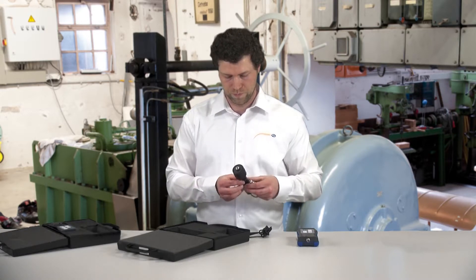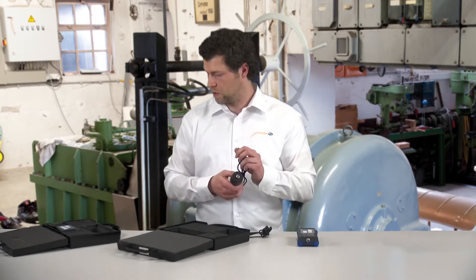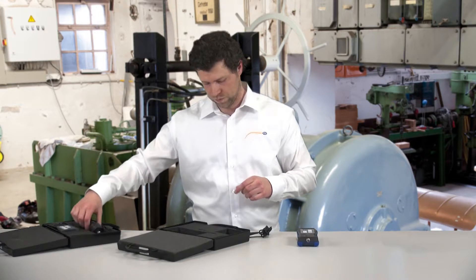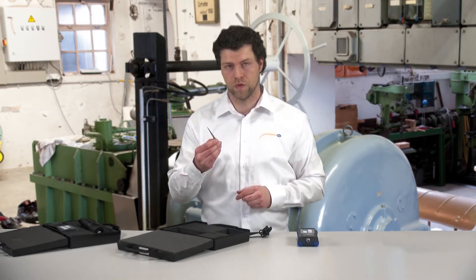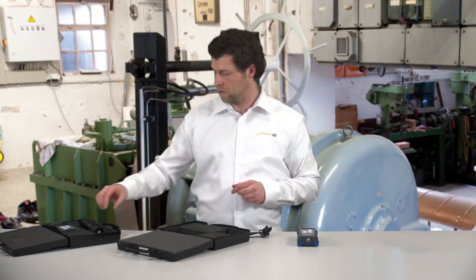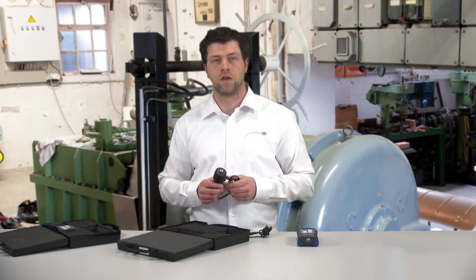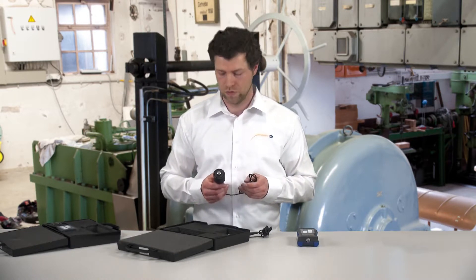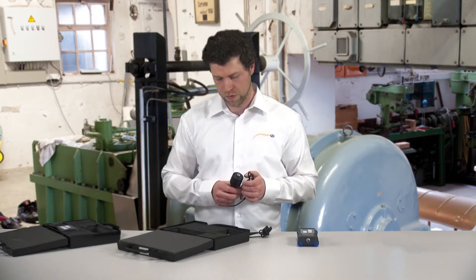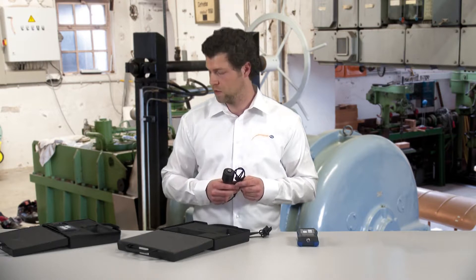On the bottom side of the handle, there is also a screw hole. Into the screw hole can, for example, a magnet be screwed in, or the probe tip. The measuring device is suitable for other usages, such as when the measuring area isn't accessible with a magnet, or when surfaces are non-magnetic so that no magnetic attachment can work.